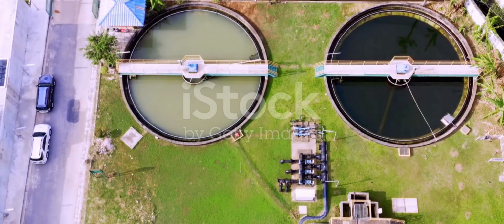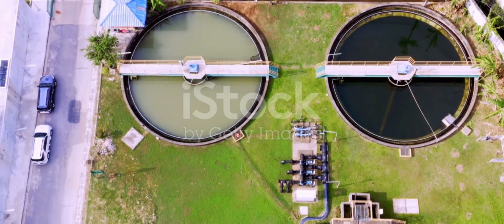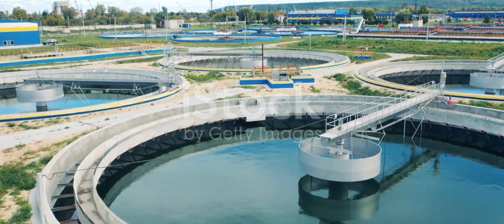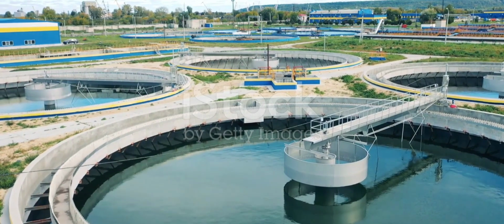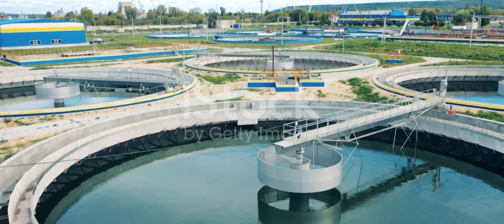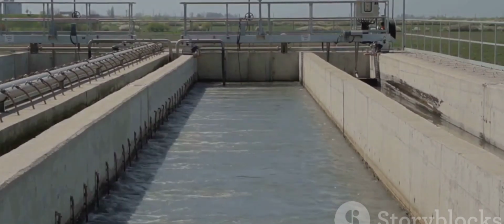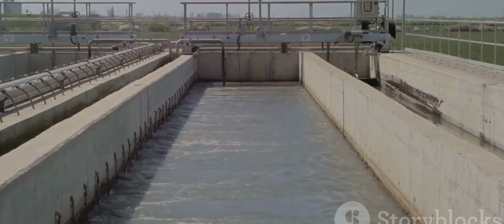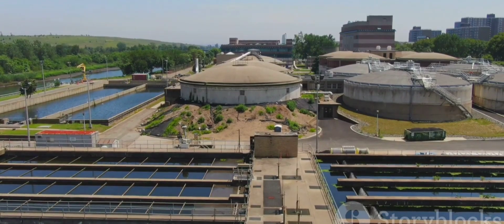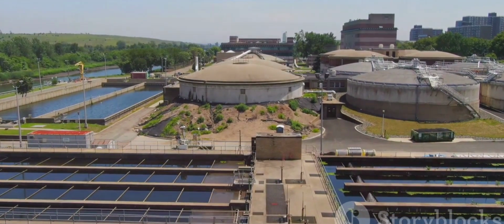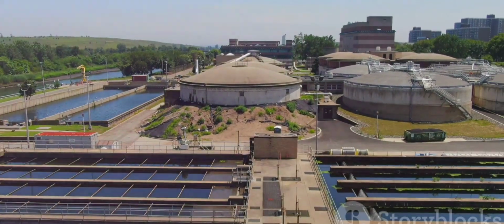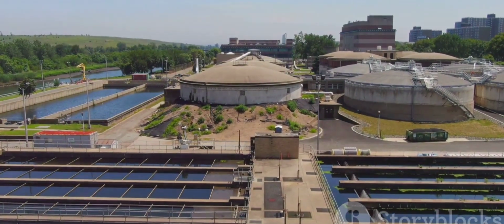The water then enters sedimentation tanks, also known as clarifiers. In this stage, the heavier floc particles settle to the bottom of the tank, forming a layer of sludge while the clarified water moves to the next stage. Key parameters to monitor include settling time, measured in hours, sludge volume, overflow rate in cubic meters per square meter per day, and the turbidity of the clarified water.